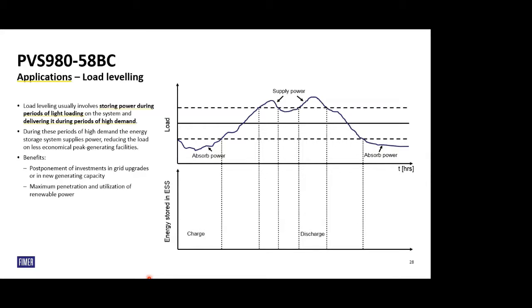You can have something called load leveling. I would say you should perform this at an 11 kV or 33 kV distribution level, at a factory level or at a normal substation level. It is nothing but storing power during low or light loading periods, where the load is low, and using it to shave off the peaks, thereby reducing the burden on the grid infrastructure. So how do we do it?